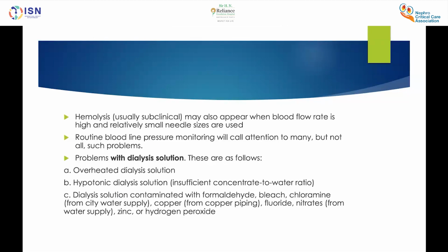There can be problems with the dialysis solution, that is overheated dialysis solution, hypotonic dialysis solution, or dialysis solution that's contaminated with formaldehyde, bleach, chloramine, which could be from the city water supply, or from piping contaminated with copper, fluorides or nitrates, zinc or hydrogen peroxide.